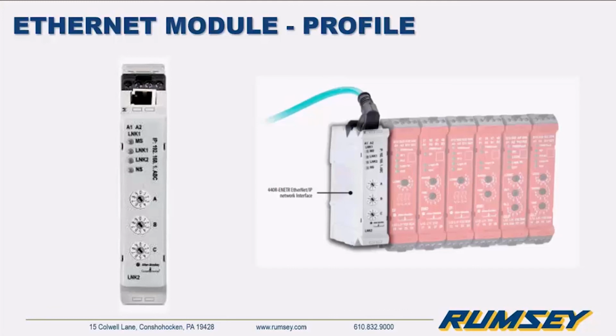Where its true value is shown is when you bring in this Ethernet module, and this is paired with GSR relays like the DG relay, the dual GuardLink, and it is connected with an optical bus. So on the back end of the Ethernet module, there are little taps that hook into the relay, and it's able to communicate that way. Essentially, it has an embedded switch at the top, so it supports device level ring topologies, and the 3 rotary dials there are to set the IP address of the system.